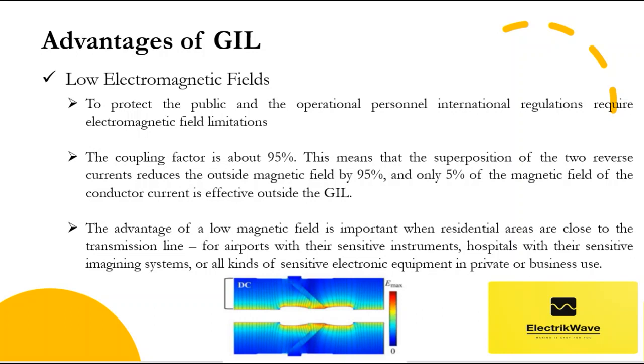In case of limitation of the magnetic field in the surroundings, this solidly grounded GIL can fulfill even very low magnetic field requirements. With a current rating of 3,150 ampere, within a few meters distance, a magnetic field strength of one micro Tesla can be reached, as required in some countries. The advantage of a low magnetic field is important when residential areas are close to the transmission line, for airports with their sensitive instruments, hospitals with their sensitive imaging systems, or all kinds of sensitive electronic equipment in private or business use. In Italy, electromagnetic field requirements for new installations go down to magnetic flux values of only 0.2 micro Tesla, and the GIL can reach such low values over a distance of a few meters.